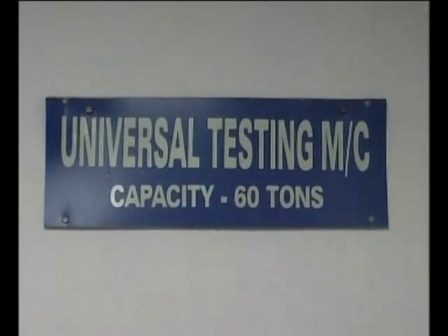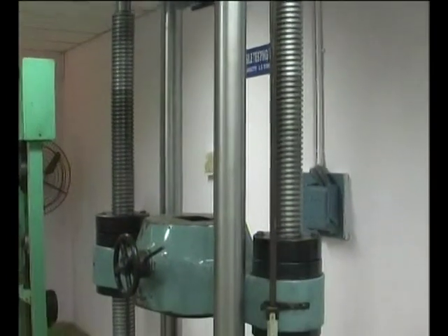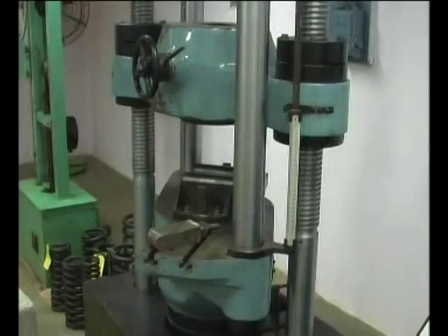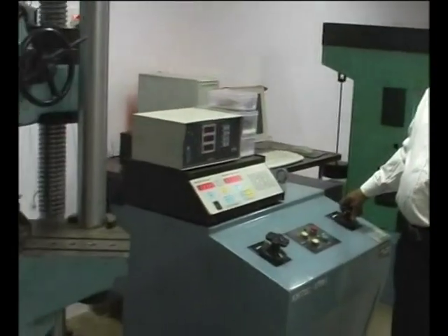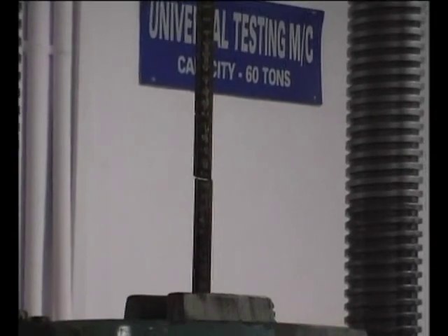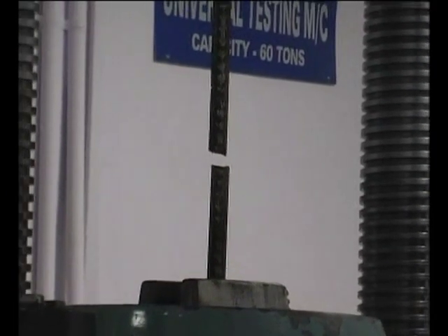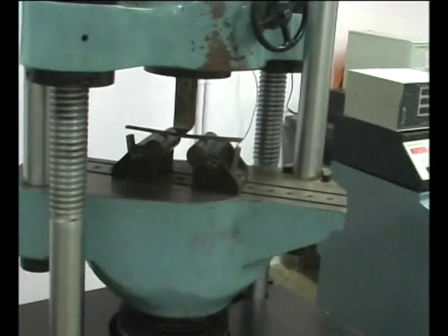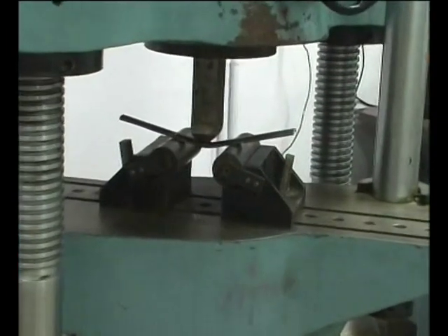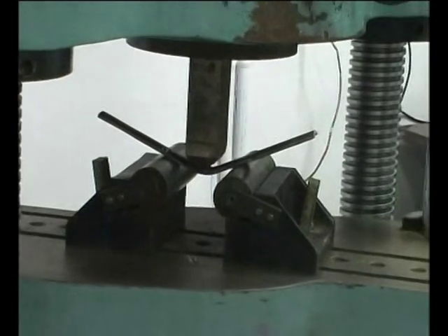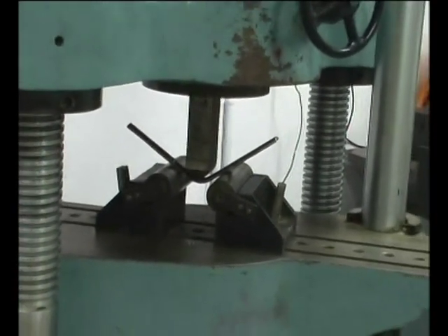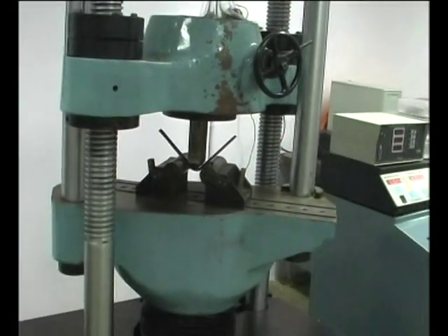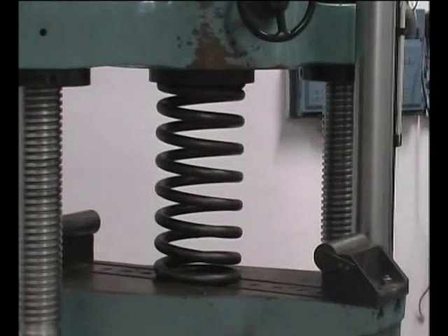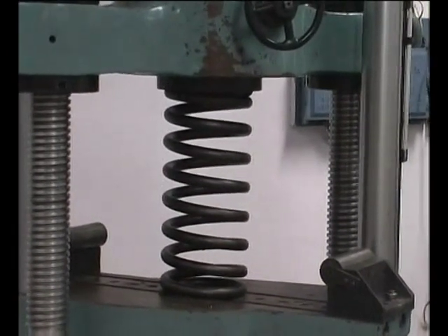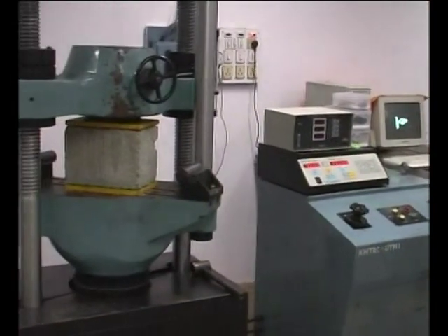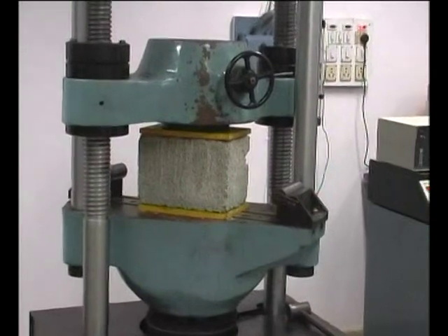Universal testing machine. This machine has the capacity of 60 tons and is useful to test ultimate tensile strength, percentage of elongation, percent of reduction in area and yield stress in steel, and also 0.2% yield stress by extensometer. This machine can be used for bend tests of plates, bars and welded plates. Compression of all types of springs can be done here. Compression strength of cement concrete cubes, cement blocks and bricks can also be tested here.